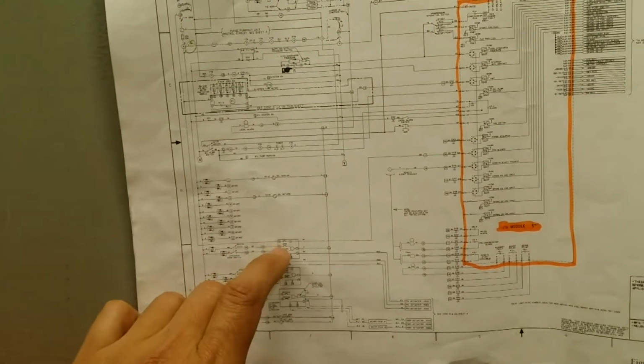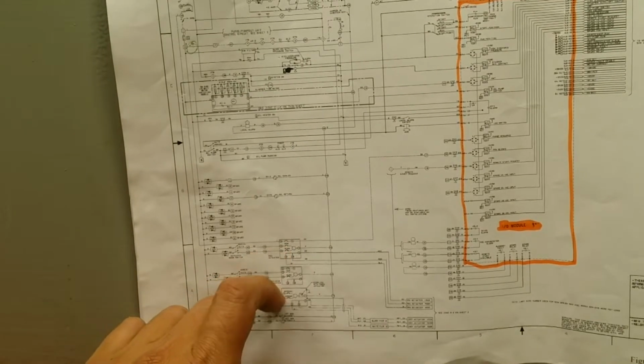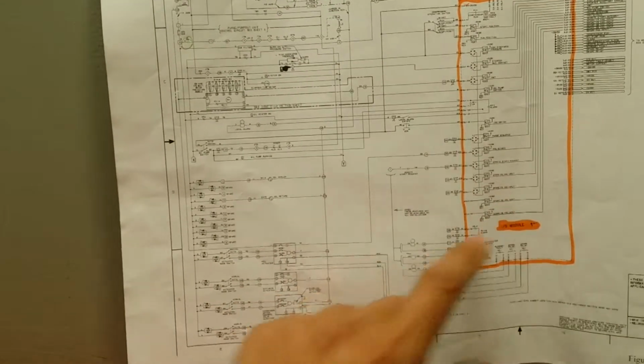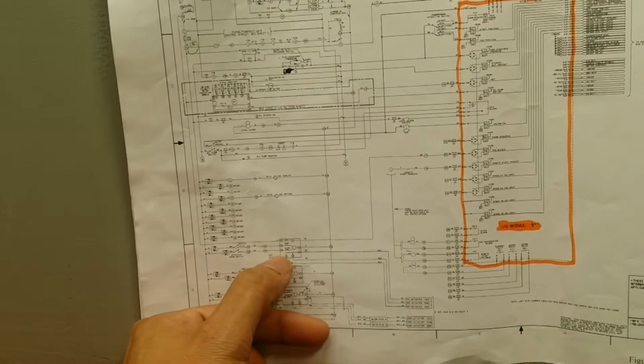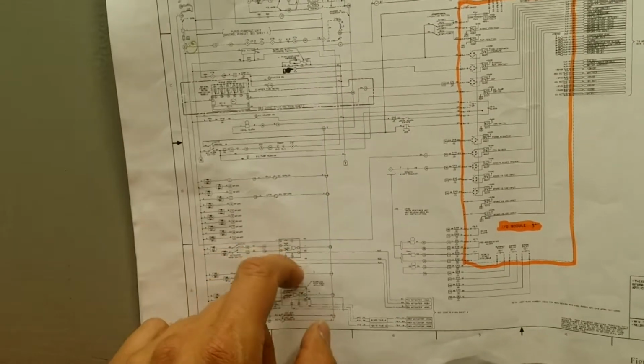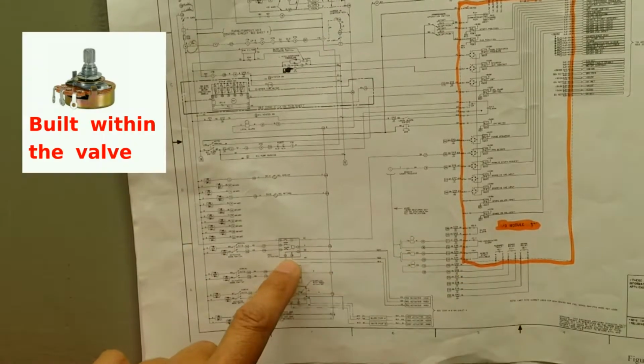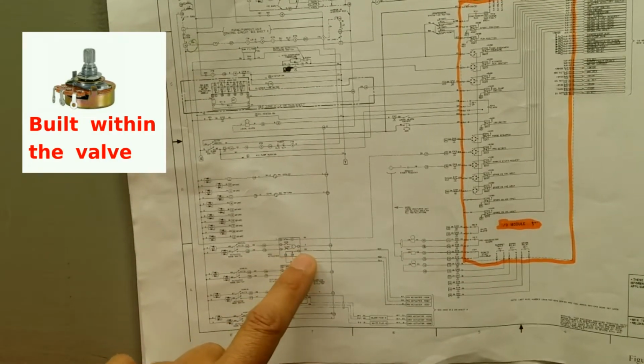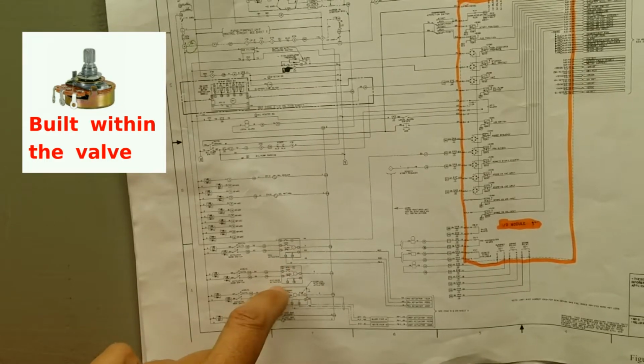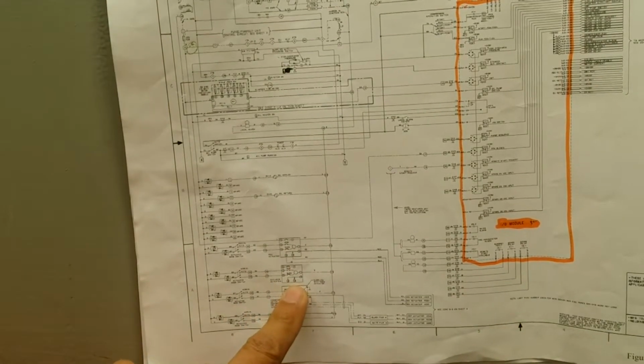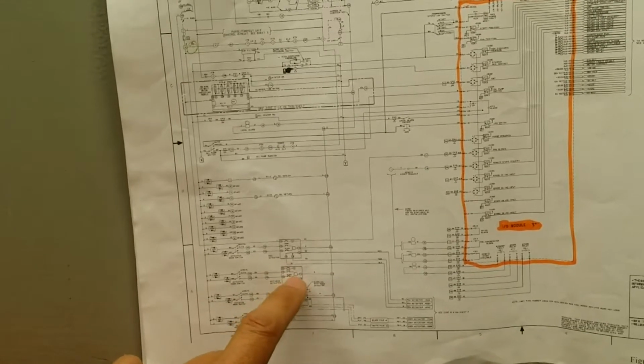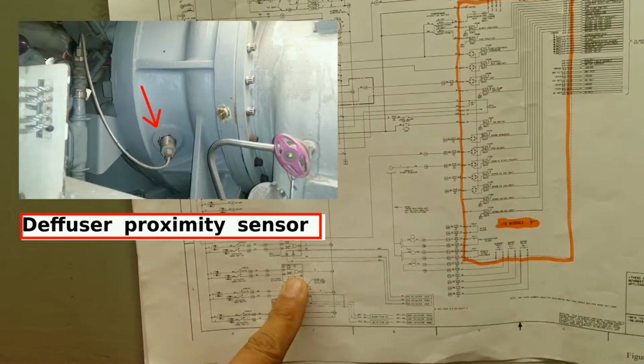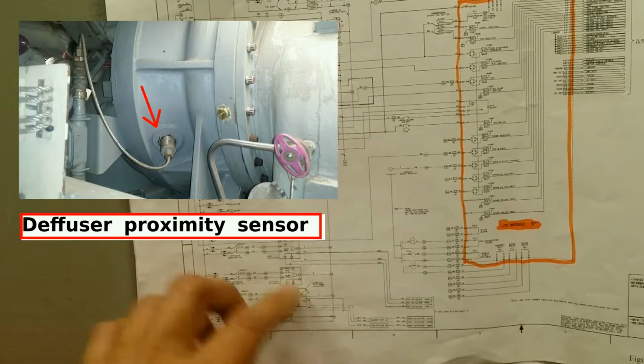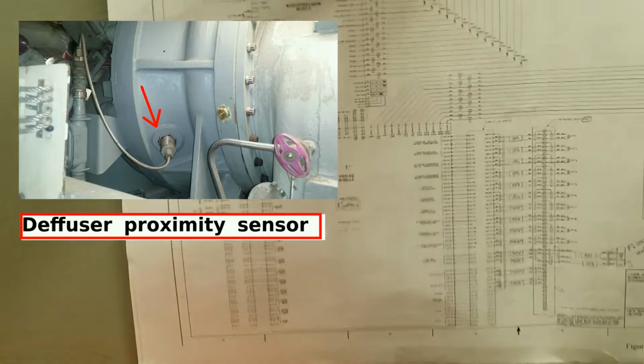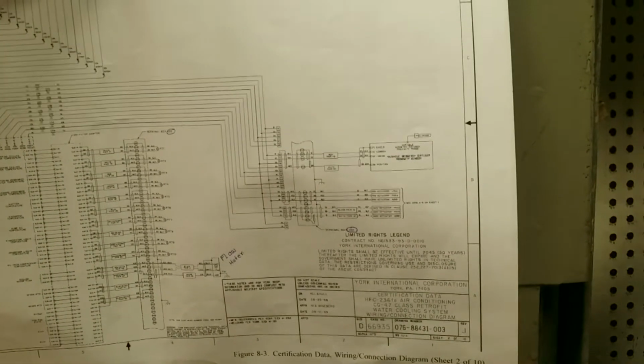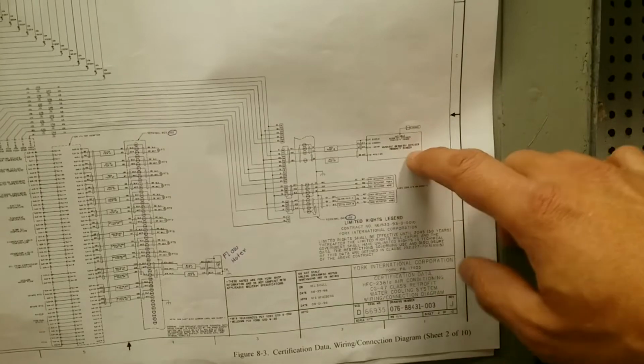I will talk more about these valves over here, but right now I covered them so you have an understanding of what I refer to in the circuit card. This is the PRV valve, and the next one is the diffuser. Notice that on the schematic, the PRV valve has a potentiometer attached to it, but the diffuser valve doesn't have one, because the distance the diffuser valve opens or closes is sensed via what is called a proximity sensor, and the proximity sensor is drawn over here.